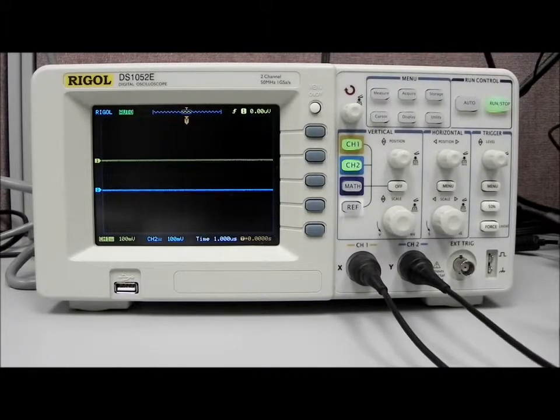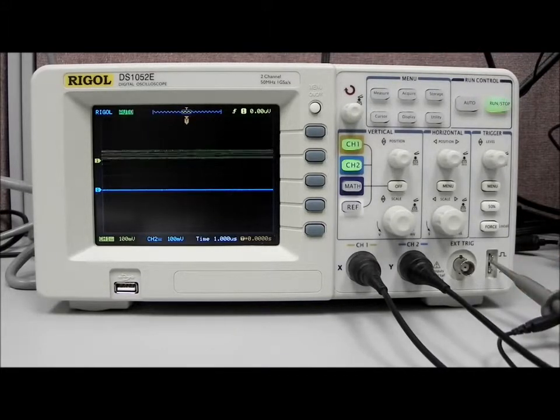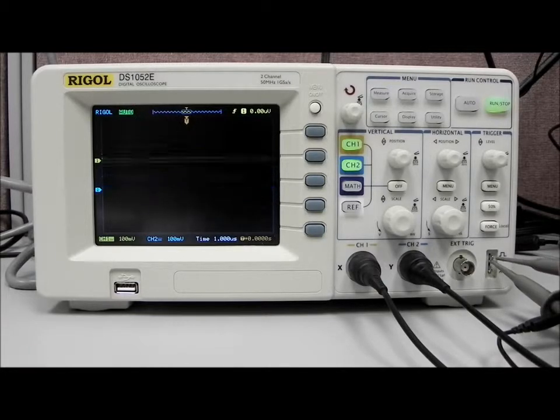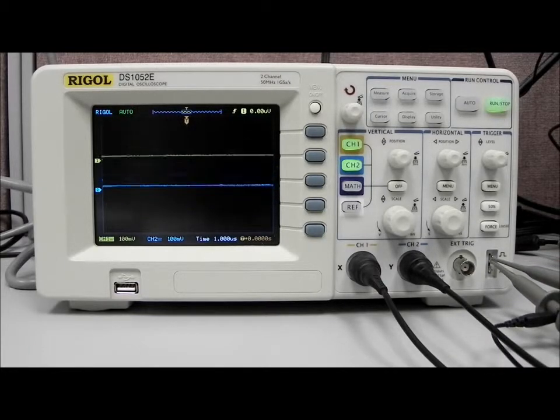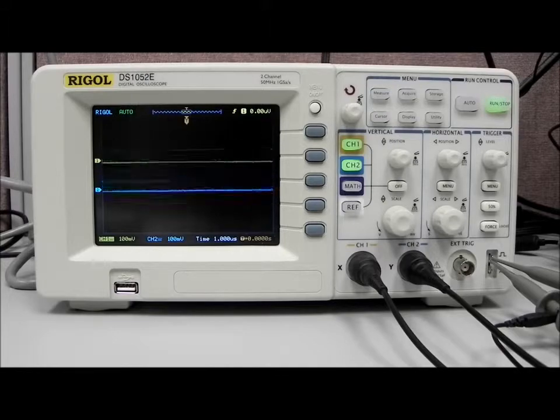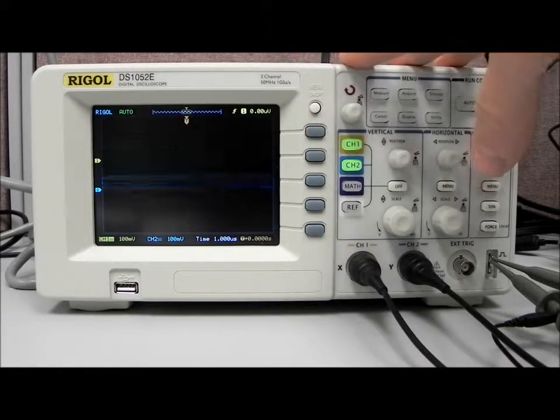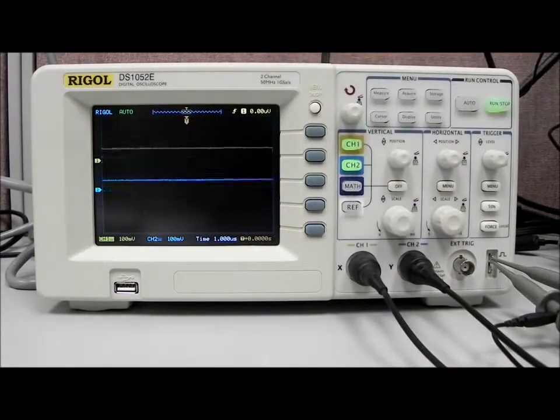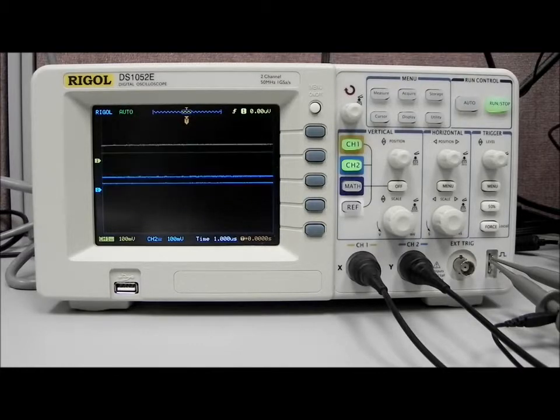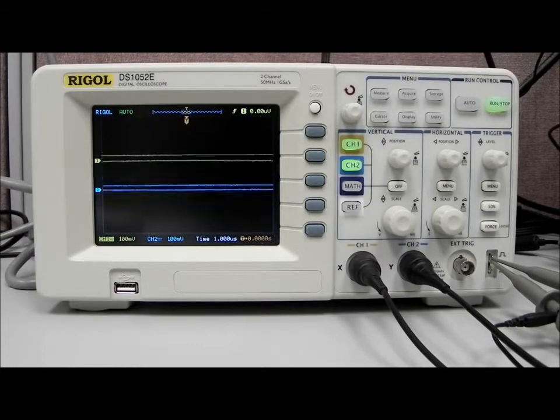First thing we're going to do is go to the probe compensation outputs here which is going to deliver a one kilohertz, approximately three volts square wave. You can see that with the factory defaults, which is where we're starting, we have a lot of, well we're not capturing the signal exactly like we would like.